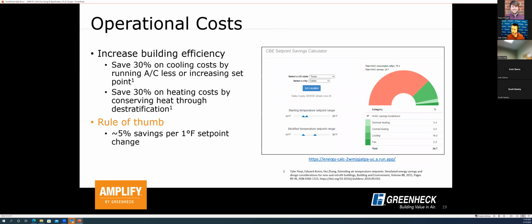On top of that, those are all first cost savings. I mentioned earlier that HVLS fans can also be used for some operational savings, in particular, increasing building efficiency. So this goes back again to the fan's ability to destratify or just reduce the need for cooling of a space. Because what we're able to do is, again, change our design conditions in that space. So in a cooling scenario, in a summer month, you can save upwards of about 30% on your cooling costs just by running the AC less frequently, or again, increasing your temperature set point in the space so that we're maintaining a higher temperature, but we're using the HVLS fans to help people feel like they're at that original design condition temperature. So this is very effective.